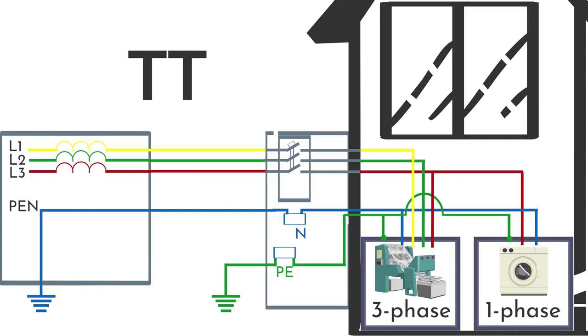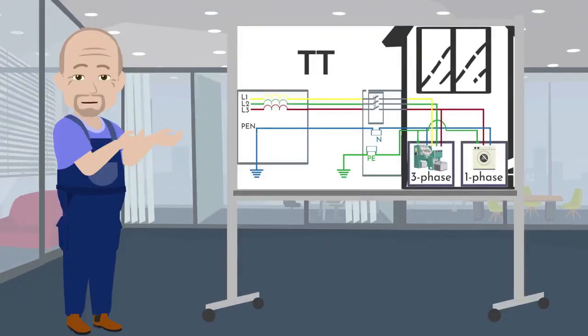This conductor is solidly grounded at the substation power supply source. While power cable inside the house has four cores, three phase conductors and a functional zero conductor. The exposed conduction parts of the appliances are grounded by a pin-type ground terminal. For this system, you must carry out a thunderstorm protection measure and install an RCD.